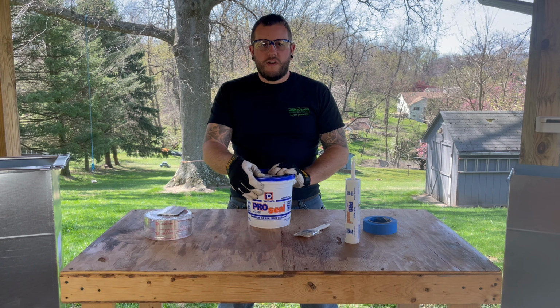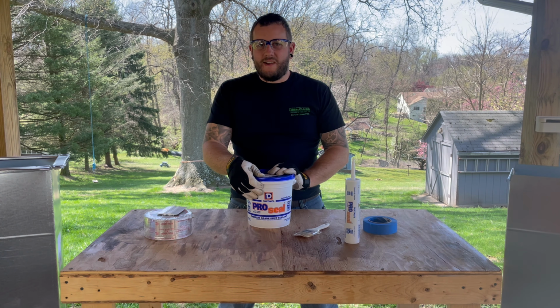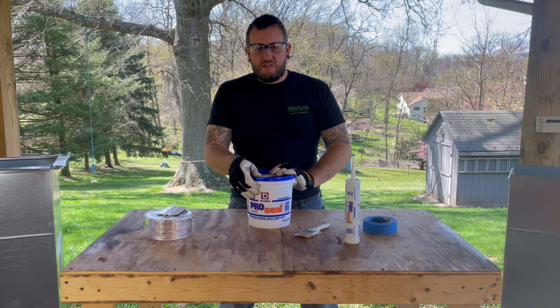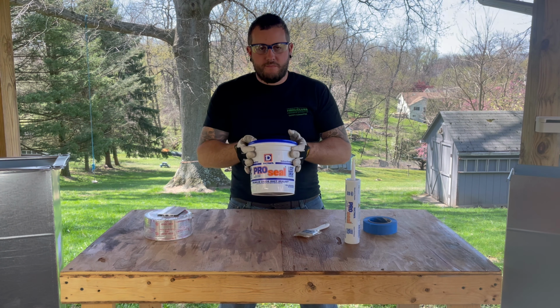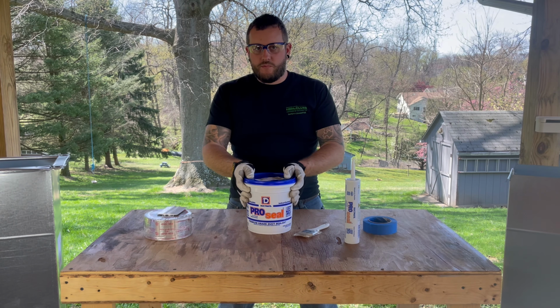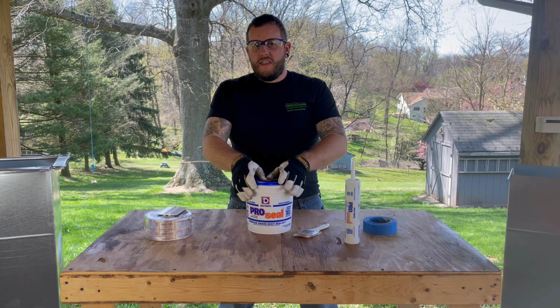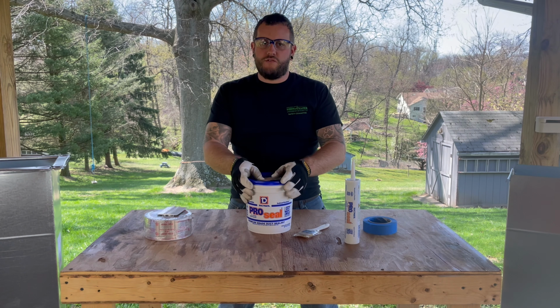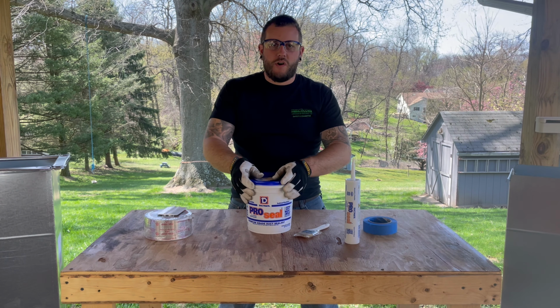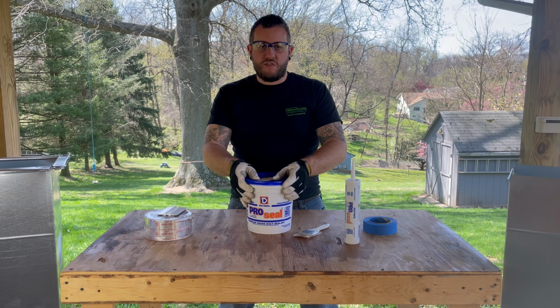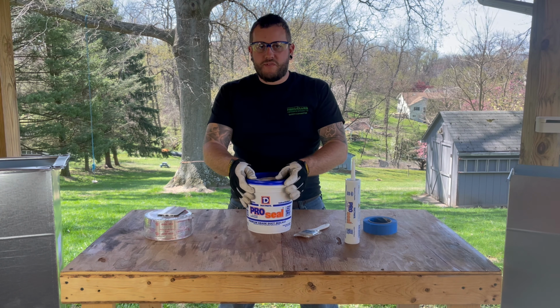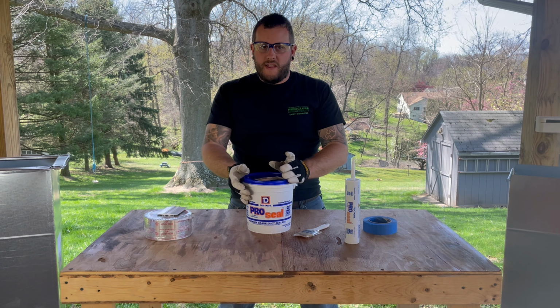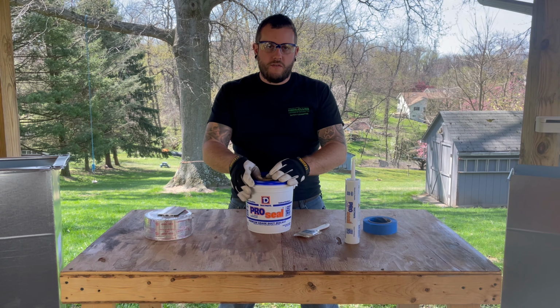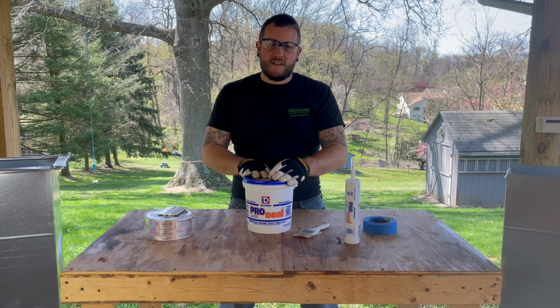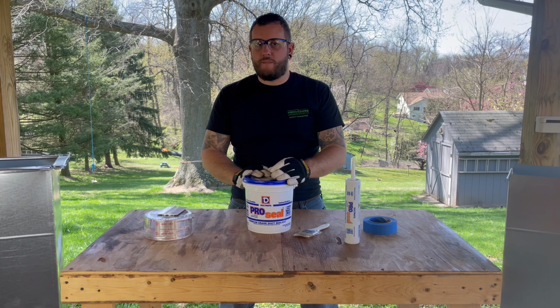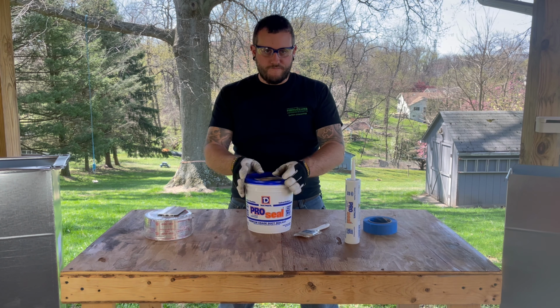When it's on the ductwork, we do not want the ductwork to get wet. So if this is an exterior application, we cannot be using this particular Pro Seal. They do make a Pro Seal that's for exterior applications. The more common issue is when you're installing this in a building and the GC wants you to turn your air conditioning on to temper the building, and we don't have the insulation complete, your ductwork can sweat. That sweating will make the duct seal become liquid again and drip off of the ductwork.